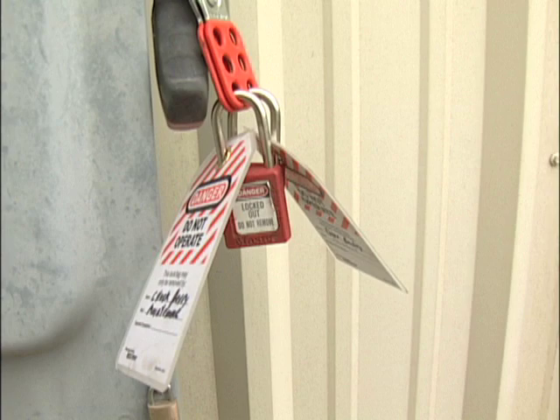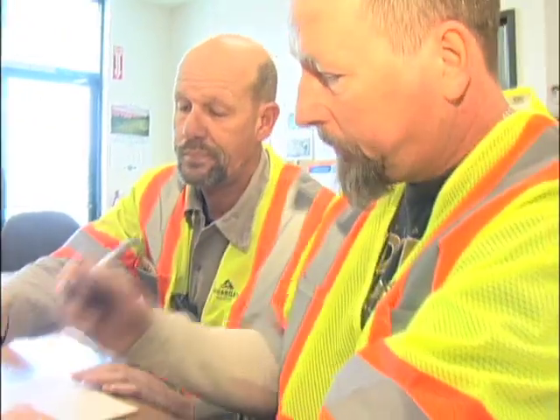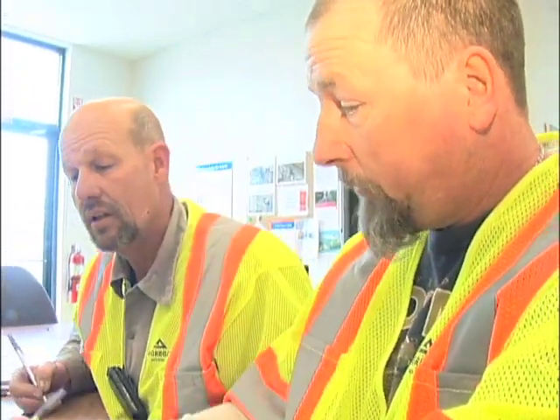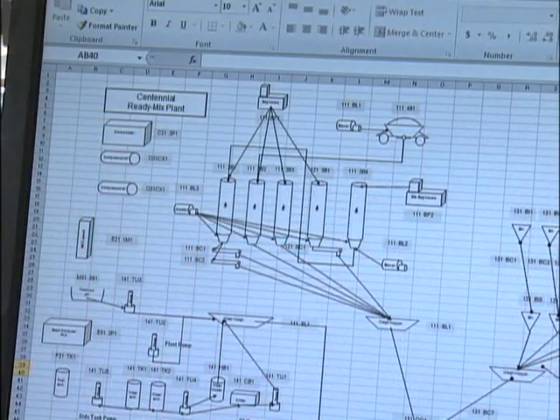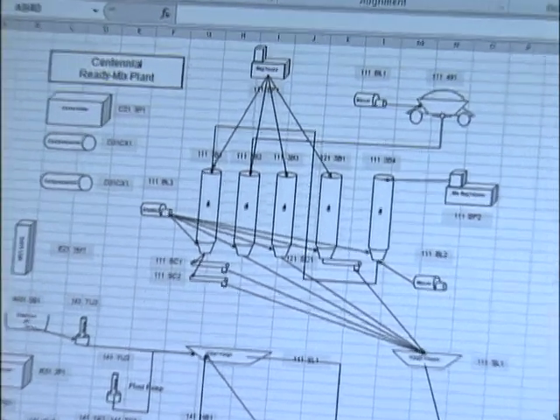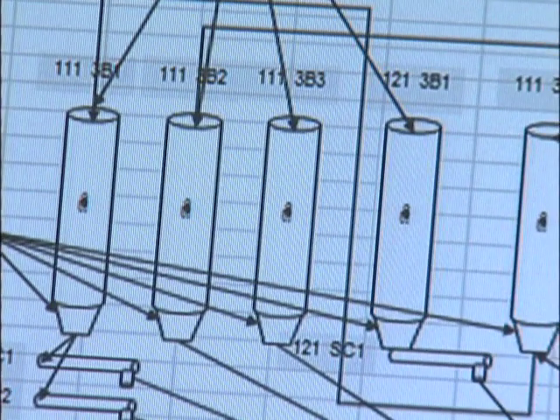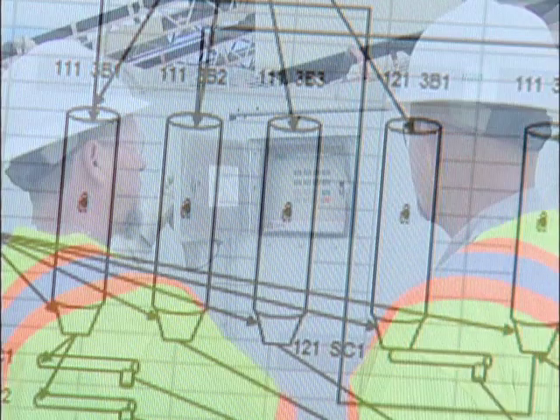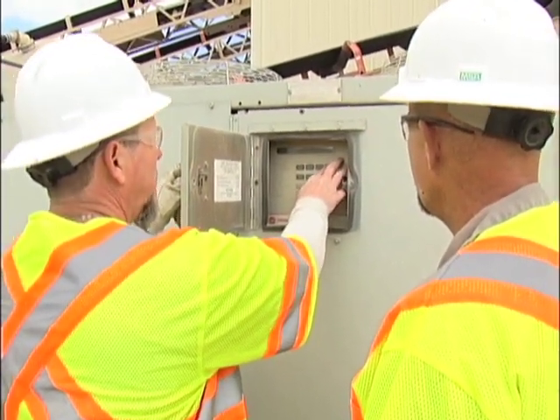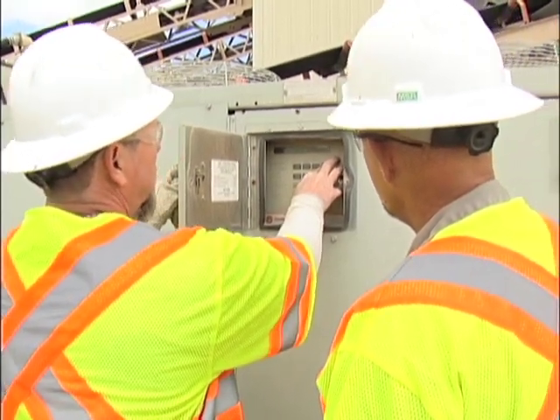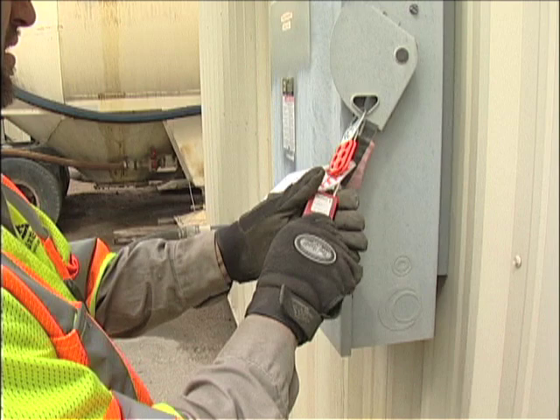Number 3. Now an authorized and/or affected employee must turn off or isolate all energy sources to the equipment to be inspected or worked on. Number 4. At this point, all appropriate lockout, tagout devices must be correctly identified, labeled, and then applied to correct locations to ensure energy isolation to the correct equipment. Indeed, multiple devices may need to be applied in multiple locations. Number 5. Any and all stored energy must be completely secured and/or released. Number 6. All employees should verify all forms of energy isolation.